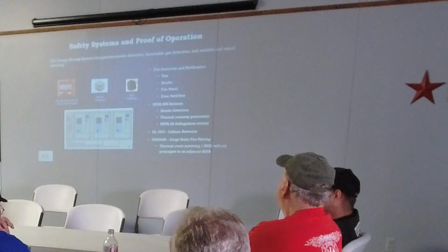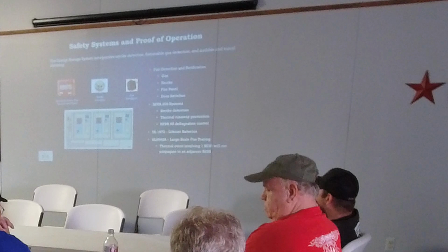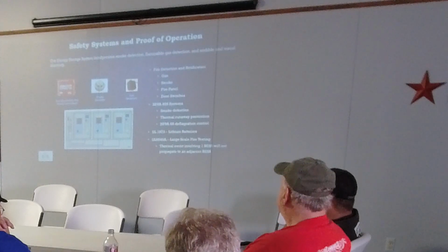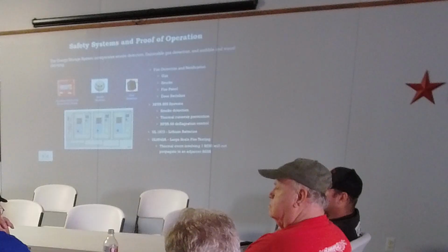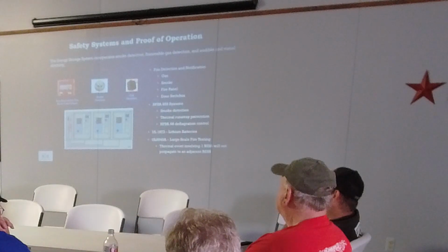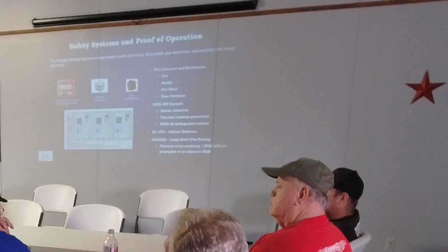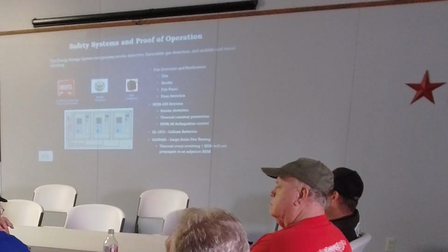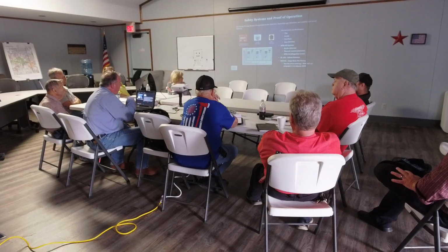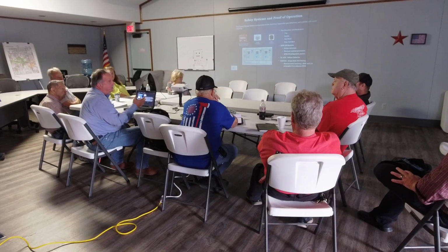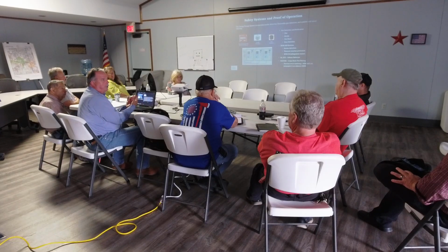Again, we incorporate smoke and flammable gas detectors, fire panels, door switches. These things are locked and secured, requiring special tools and equipment for technicians to even get in. Even if a door were to open, it immediately shuts that system down. The one drawback for my fire department friends is even if I shut the battery off, there's still stored energy. The battery still contains all the energy it has, which is another reason we aren't prepared or equipped to go in and poke around.